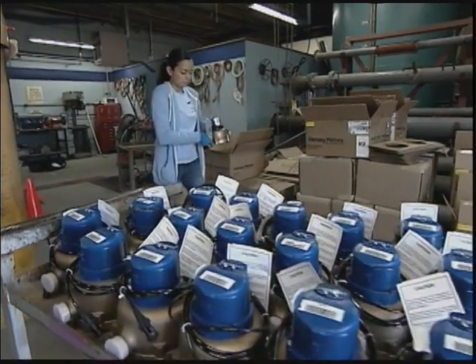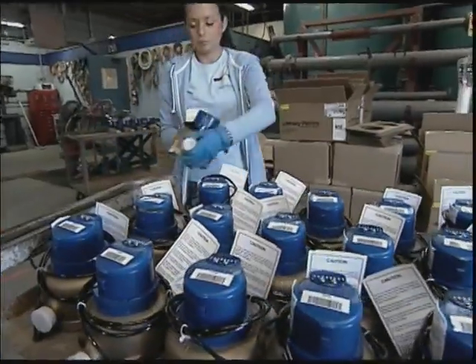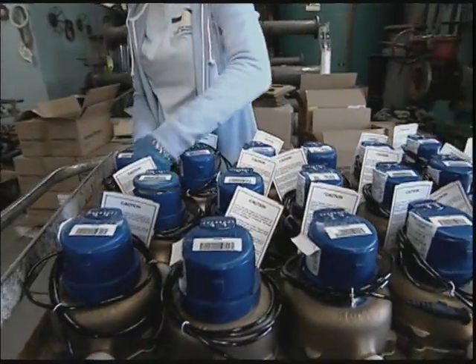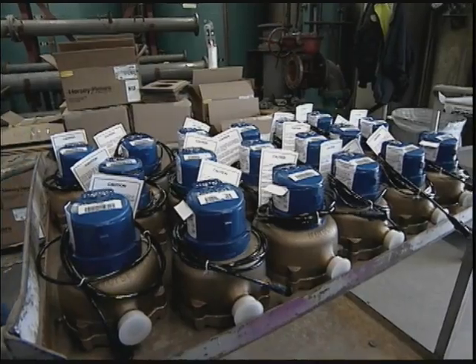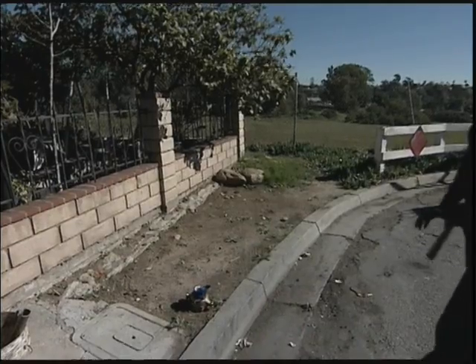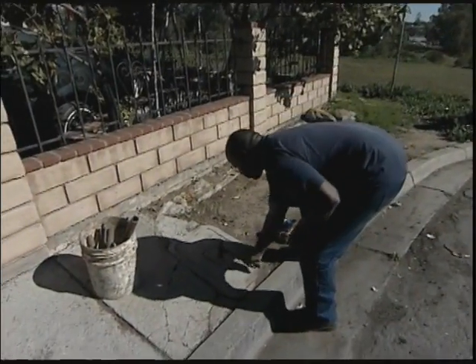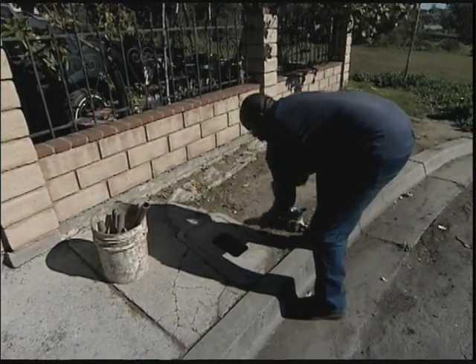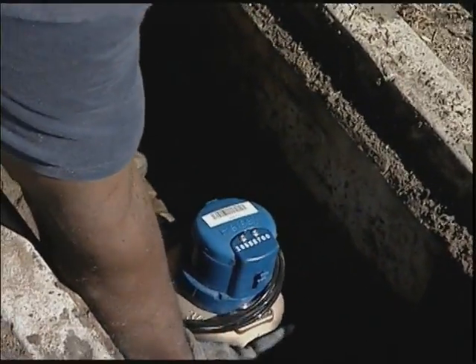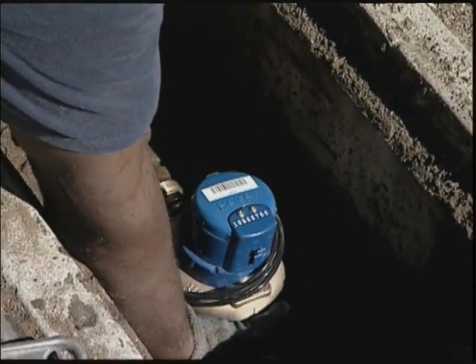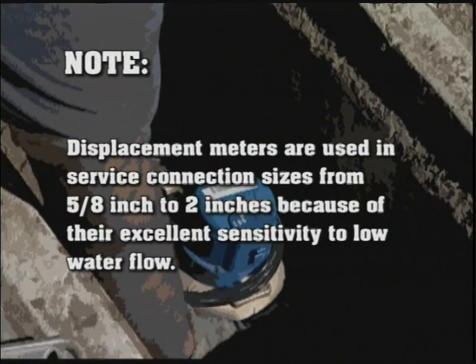Experience has shown that displacement meters are very effective in their accuracy, long life, simple design, moderate cost, and easy maintenance. Tens of millions of these meters are in use today. Displacement meters are used both for residential and small commercial applications in service connection sizes from 5/8 of an inch to 2 inches, because of their excellent sensitivity to low water flow.